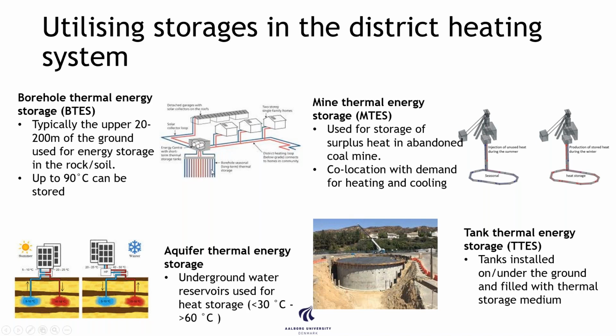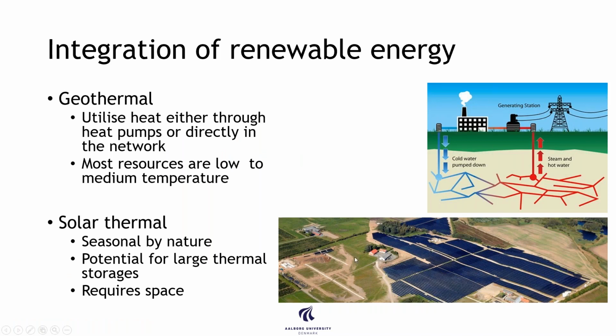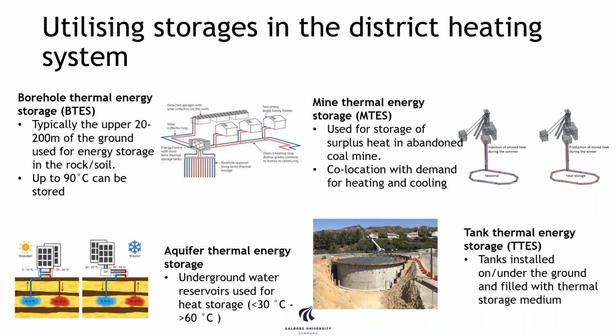One that I have not mentioned here, but it's very common in Denmark, and it's also situated around this case here, is simply a pit storage, where you dig a hole in the ground and you insulate the hole, and then you fill it up with water. So it's a very simple, cheap technology to implement, and probably cheaper for now than many of these options.